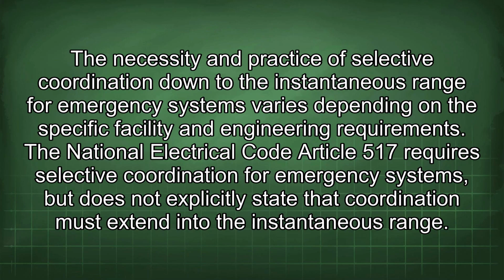The necessity and practice of selective coordination down to the instantaneous range for emergency systems varies depending on the specific facility and engineering requirements. The National Electrical Code Article 517 requires selective coordination for emergency systems, but does not explicitly state that coordination must extend into the instantaneous range.